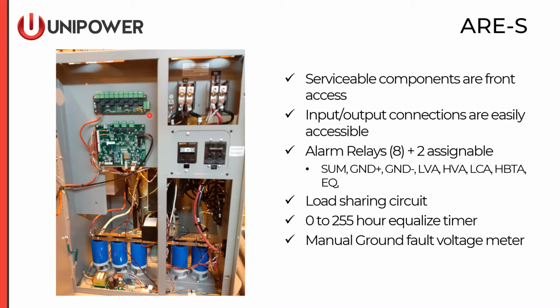And this time, we go a little further in providing 2 user-definable custom alarm relay outputs. And with the custom relay outputs, these can be programmed to change states with any available and assignable alarm threshold or system event, to include equalize, summary, ground fault, positive, negative, LVA, HVA, LCA, and high battery temperature alarm even. Also, load sharing circuit is always included. This time, instead of a 18-gauge wire, we're using a simple Ethernet cable to tie between the 2 chargers.